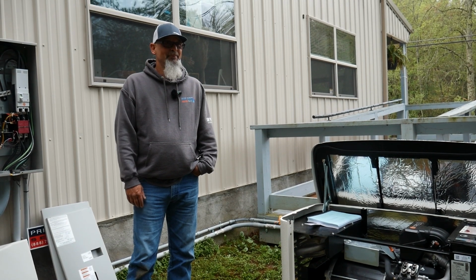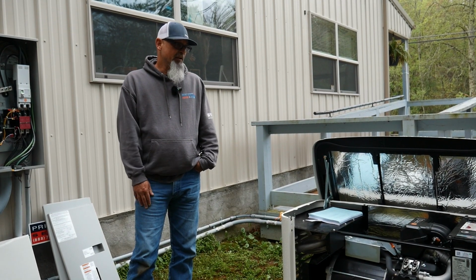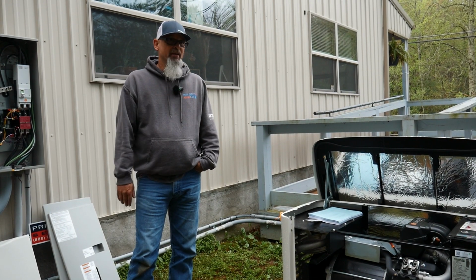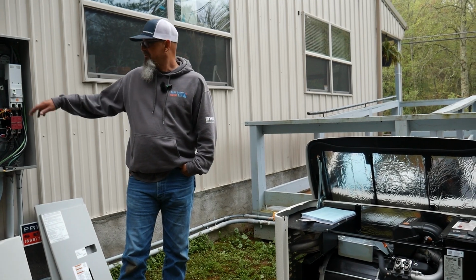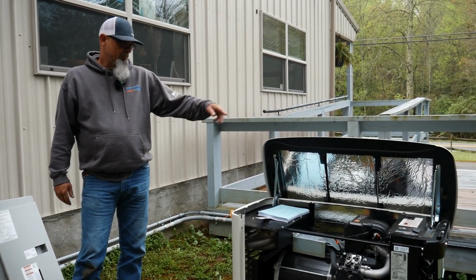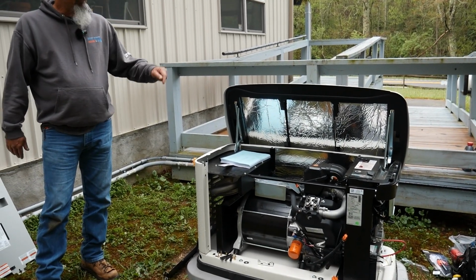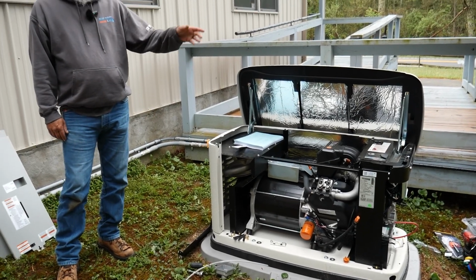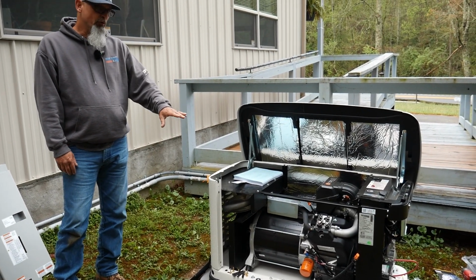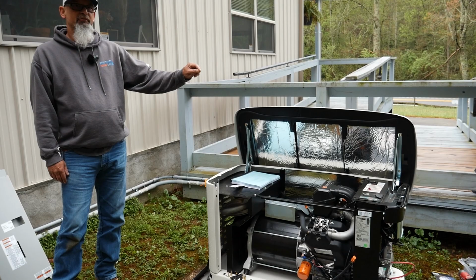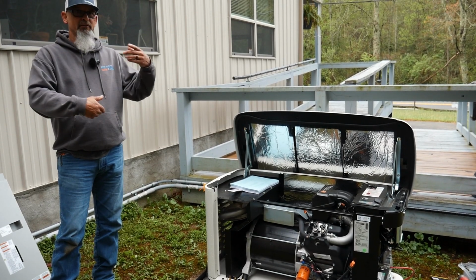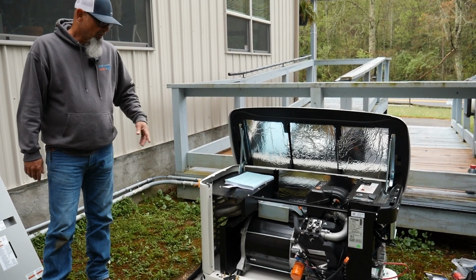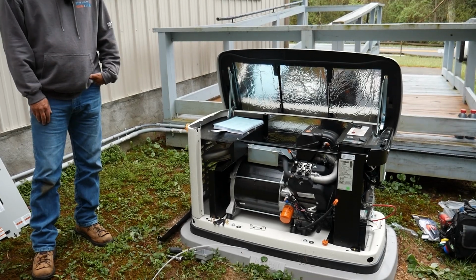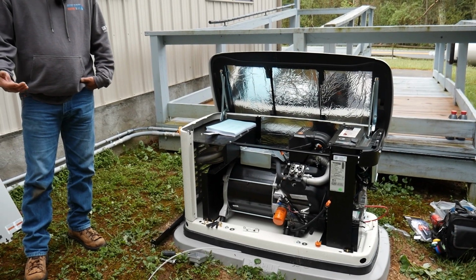It's pretty simple. Basically you start it in manual. Make sure your transfer switch is off, you got your fuse and everything plugged back up. You just hit manual, the unit's gonna start. So when you do your oil change, you'll start the unit for 2 minutes, shut it off. That way the oil is running through and it's warmed up, and it'll be a lot quicker to drain. Other than that, that's it. It's pretty simple.